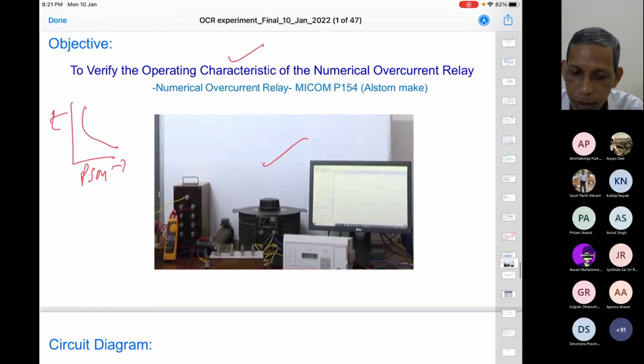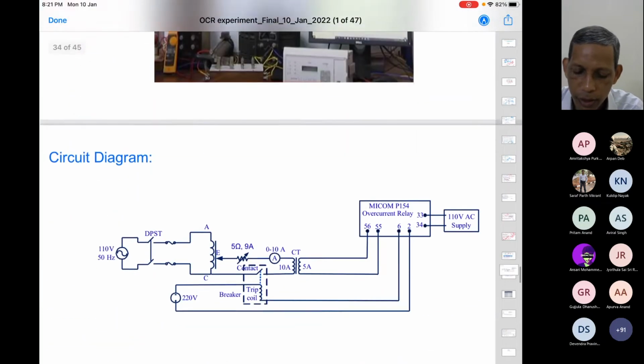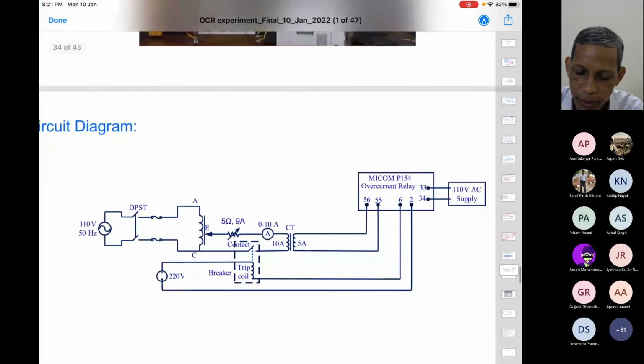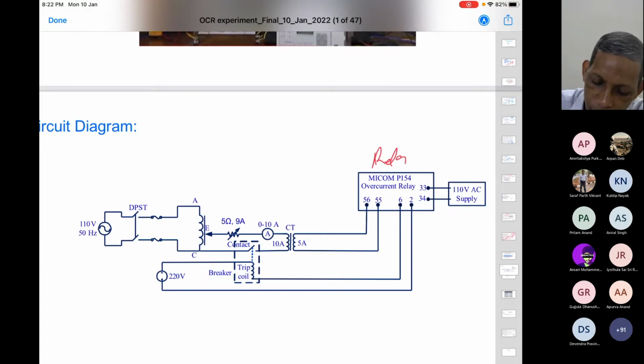So same arrangement as I already mentioned, we like to have the physical circuit diagram like this. This is our relay, the MiCOM P154 overcurrent relay. And we have to inject current into this one. For that, we have an autotransformer here, some resistance controlling the current, and we have a CT here, 10:5.